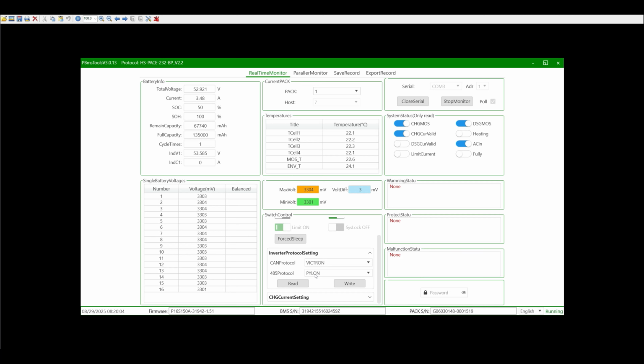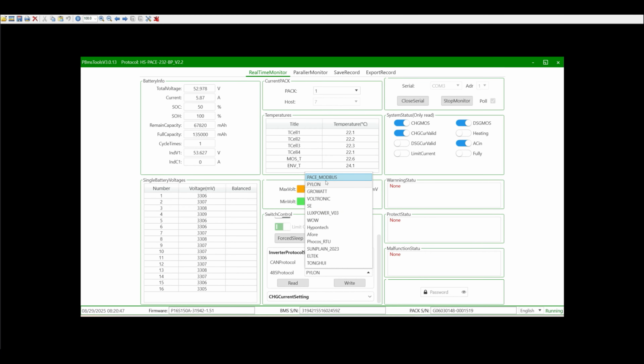On the BSL batteries, it's usually set for Pylon Tech. We're not using the RS485 port for anything else, so it's not really a problem to change that. Your CAN bus port is used for your battery communications with your inverter, so you don't want to change that at all.